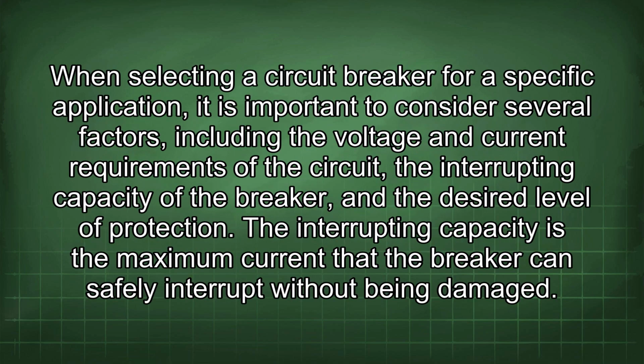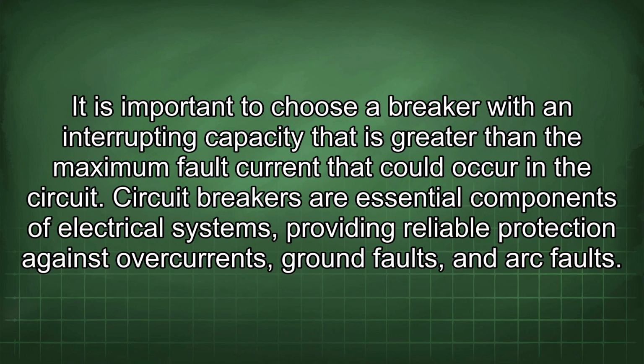When selecting a circuit breaker for a specific application, it is important to consider several factors, including the voltage and current requirements of the circuit, the interrupting capacity of the breaker, and the desired level of protection. The interrupting capacity is the maximum current that the breaker can safely interrupt without being damaged. It is important to choose a breaker with an interrupting capacity that is greater than the maximum fault current that could occur in the circuit.